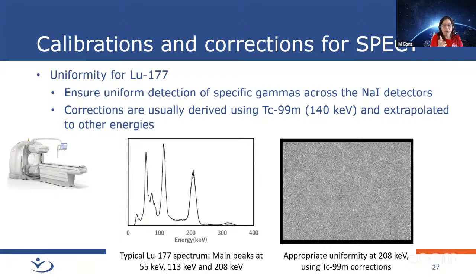If the camera is performing well, it should have a more or less uniform response across a fairly wide range of energies. So if the camera is okay, even if we have calibrated it for 140 and we decide to use the 208 peak, it should still perform okay. And that is one example here. This is a uniformity check, and that is appropriate. So even though it's been calibrated and corrected for the technetium energies, it's still a uniform and appropriate response at 208 keV. But we had to do this for all 20 plus SPECT cameras across the province.